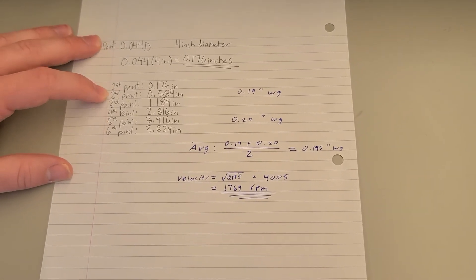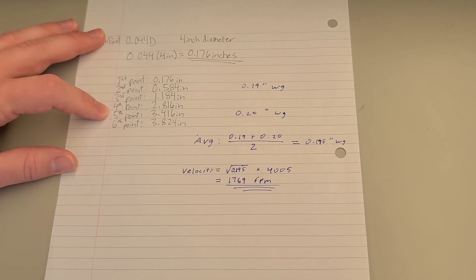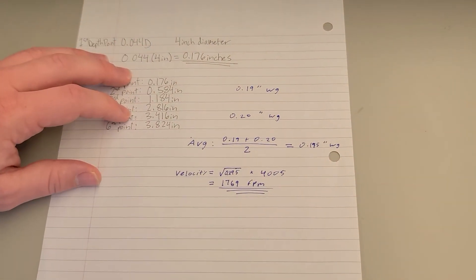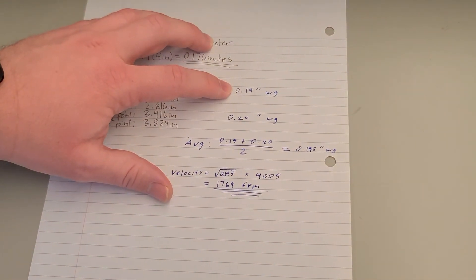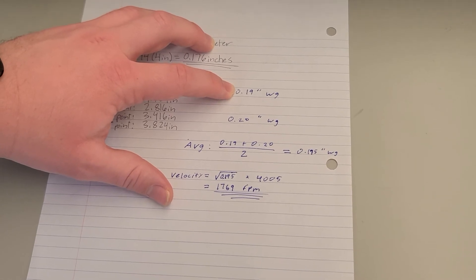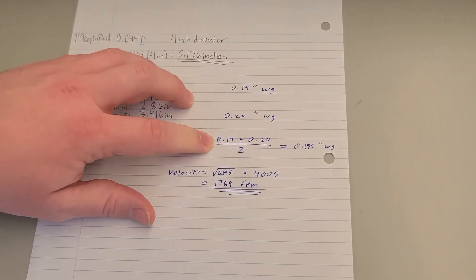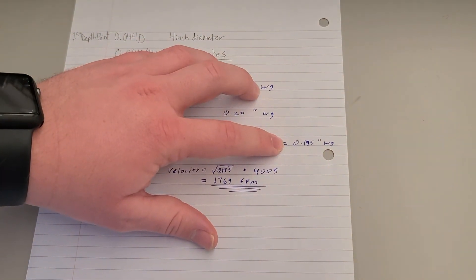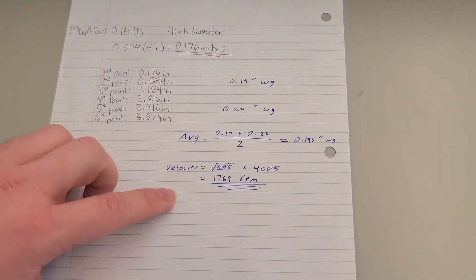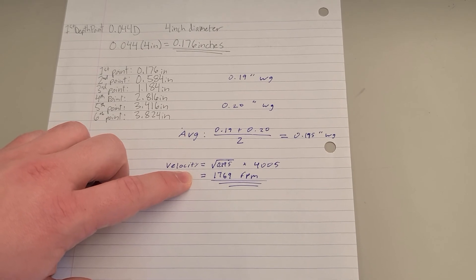Here again, we're just using the second and fifth point of the velocity traverse to show how to average those values. What we got was 0.19 inches of water gauge and 0.20 inches of water gauge. Here, we just average those together to get 0.195 inches of water gauge.